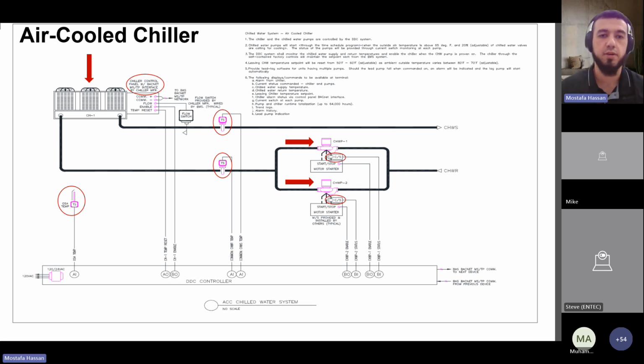There must be something out there that's going to figure out whether the pumps are on or off. We're going to get to that in a moment. But when is this system going to actually activate the chilled water pumps? It's going to go through a time schedule program, or when the outside air temperature is above 65 degrees and 20% of the chilled water valves are calling for cooling. That's how much the valve position is open. So if the valve's at 20%, then we know we need to ramp up the pumps, but also with other conditions like the outside air temperature being above 65 degrees.